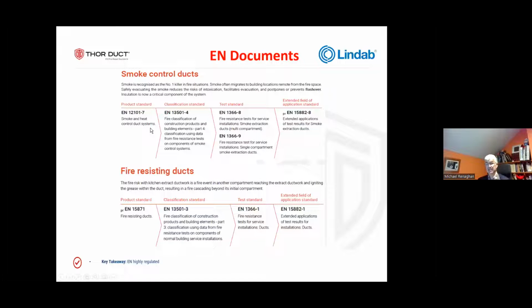It's doing something very specific in a fire test. Then we have, for everything else, fire-resistant ducts. So fire-resistant ducts cover passive, pressurization, and kitchens. A passive duct is where we can't use, for example, fire dampers. It's inaccessible. We're not going to be able to drop test them. So we can use fire duct because it acts like its own compartment. Pressurization duct, again, is where we're providing air into a building. So we want to pressurize a stairwell, for example. That needs to be fire-resisting duct. Obviously, you don't want it to fail in a fire. And then, of course, kitchen. Kitchen is a real problem and has unique risks. So again, we've got to have a duct that's suitable for that application and test it correctly. So we'll be going through that.